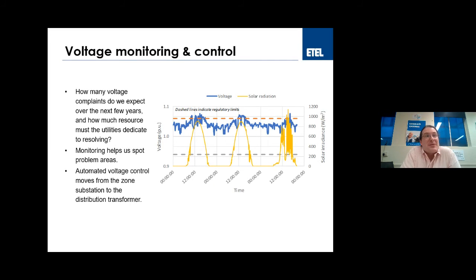This is the other issue we've seen, which is the voltage. As rooftop PV starts to drive the voltage high, most of the inverters have these set points, or trip points, where they don't export power above about 254 volts. That protects the system, but somebody wouldn't be exporting their PV, and they'll call up the utility and complain that they're not getting their outputs, and then the utility has to do something about it.